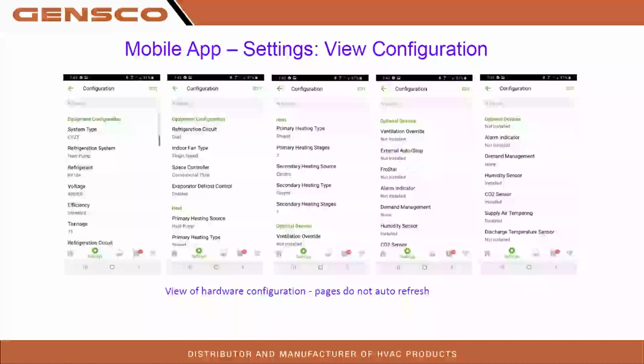This will look for that customer connections polarity. That's for accessories like clogged filter and whatnot. So that is an external. We don't use that if we are using a third party. We're going to land it on that J18 on the Symbio control. If you enable this and you don't have that customer connections options module, it'll prompt you with an alert, right? So frost stat, that comes on all of them. So that's going to be installed.